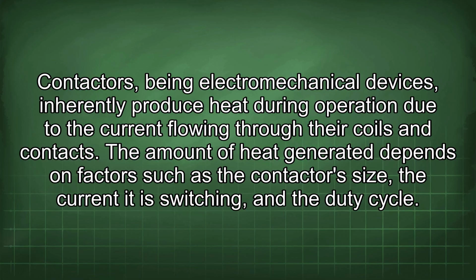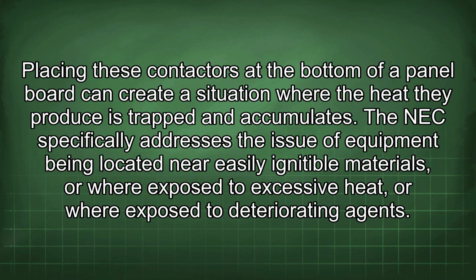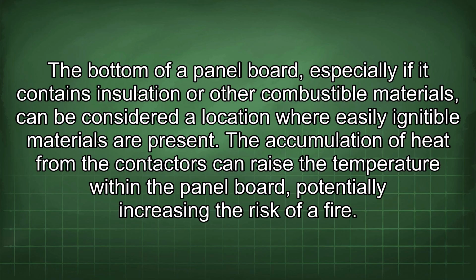The amount of heat generated depends on factors such as the contactor size, the current it is switching, and the duty cycle. Placing these contactors at the bottom of a panel board can create a situation where the heat they produce is trapped and accumulates. The NEC specifically addresses the issue of equipment being located near easily ignitable materials, or exposed to excessive heat, or exposed to deteriorating agents. The bottom of a panel board, especially if it contains insulation or other combustible materials, can be considered a location where easily ignitable materials are present.